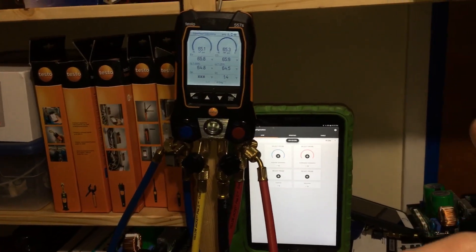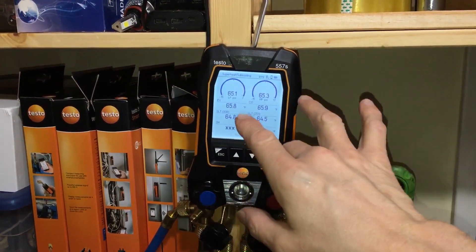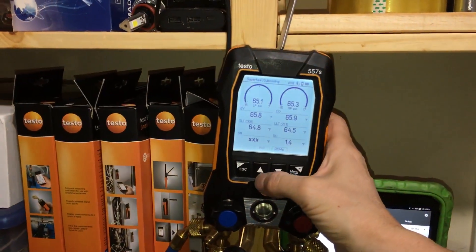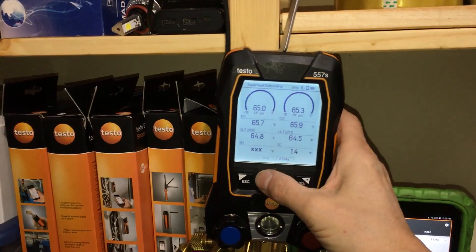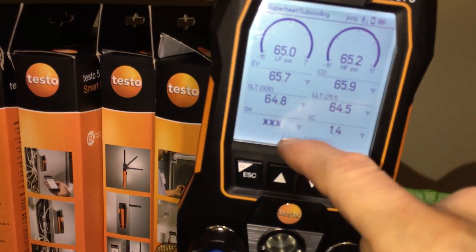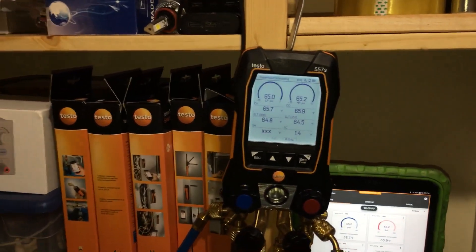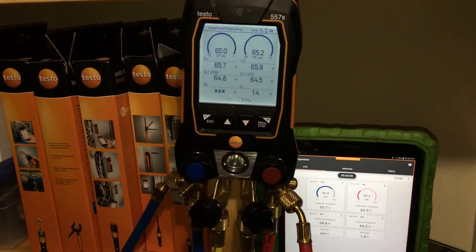So that's about it. I basically wanted to answer Richard's question about his gauges being stuck on two pressures and not being at 0-0 — and that would be pressing the auto-zero. I wonder if the auto-zero works at high pressure. Let's see — that's auto-zero with 65 PSI in there. No, I didn't think it would. The dots on the display are all faded out in a light gray, and it knows you have high pressure and you're trying to zero it. That's their way of not letting you auto-zero at higher pressures. See you guys.